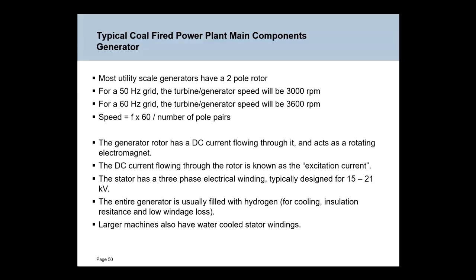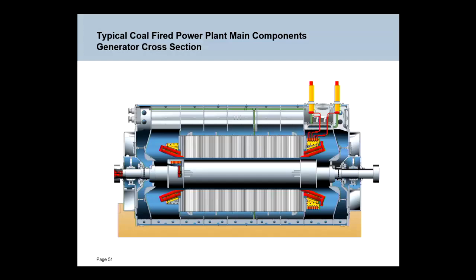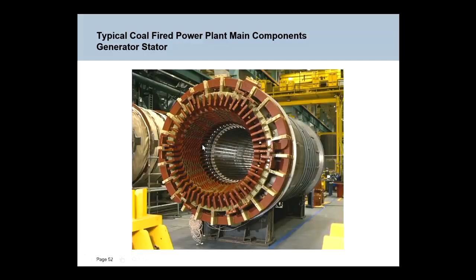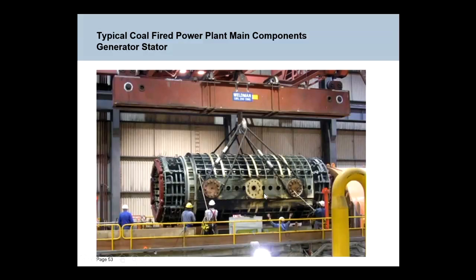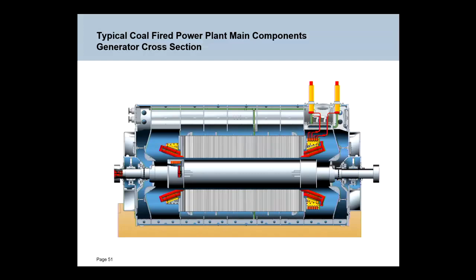Also 2-pole generators. The way the generator works, this is a cross-section of a generator. I'm just going to flick backwards. That's what the stator looks like. So the stationary circular part looks like this. It has stator windings in it and thousands of laminations of stainless steel, and the windings cut those laminations. This is what a big stator looks like on a crane. That's a 500 megawatt stator. So if we flick back to here, so this is a cross-section. You can see here are the stator windings. They go the length of the stator.